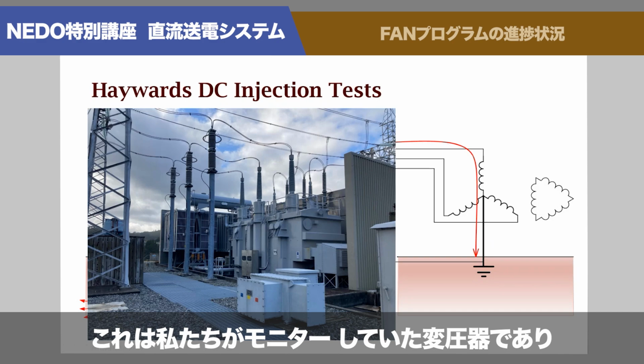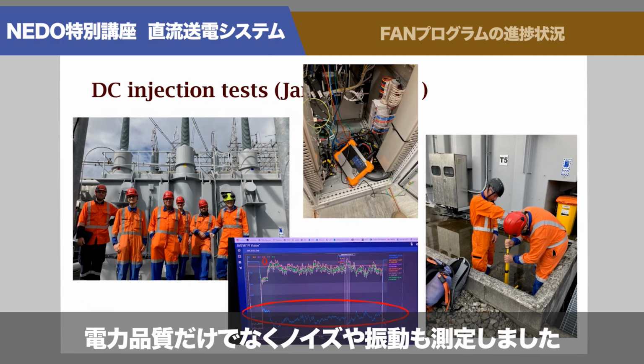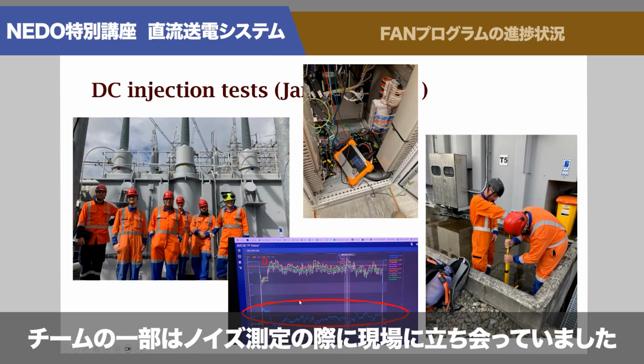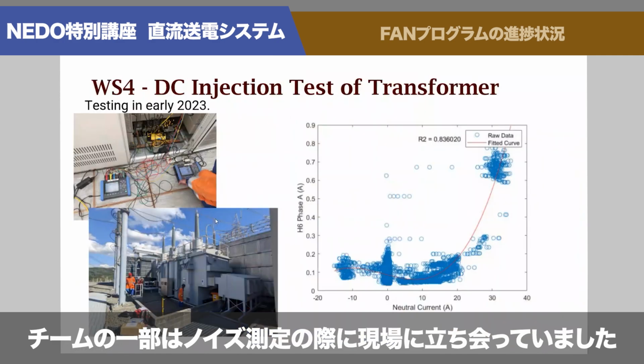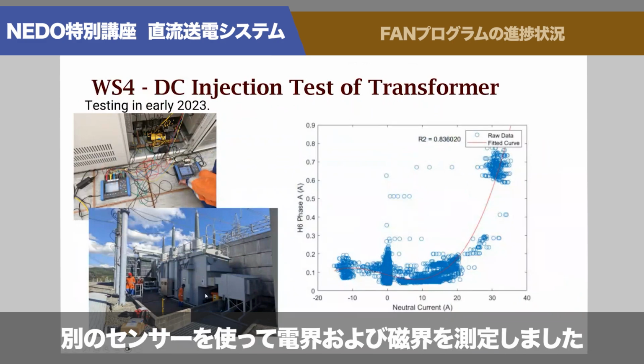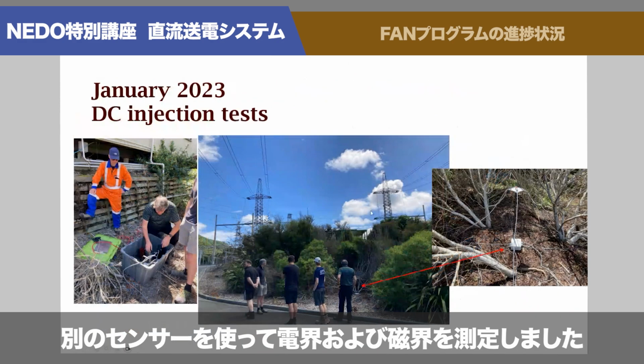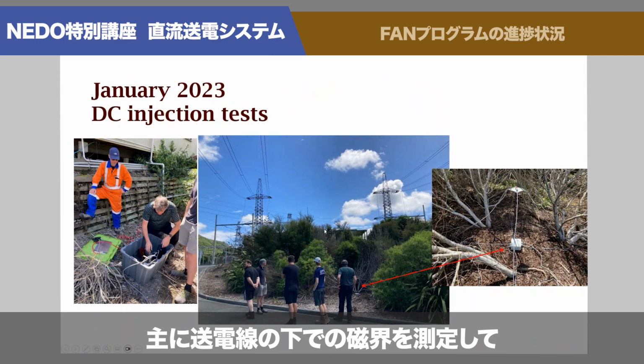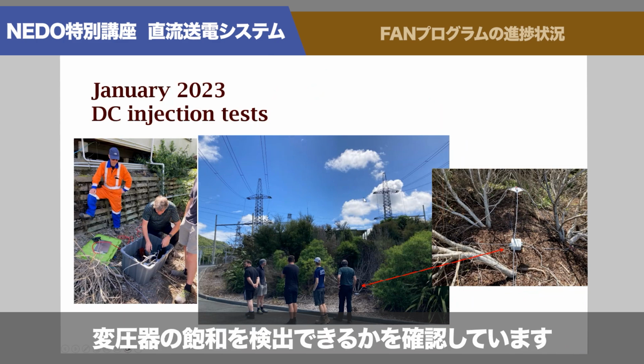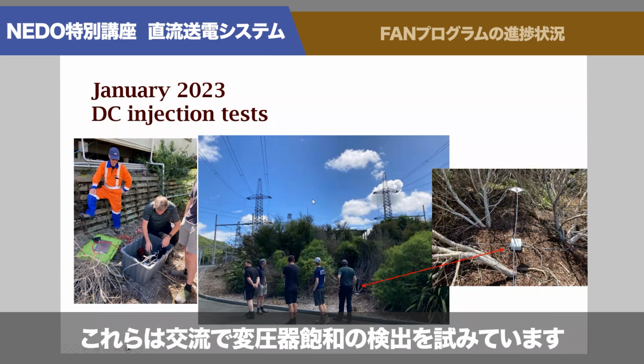This is the transformer we were monitoring and looking at. We not only measured the power quality, but we measured noise and vibration on it. Some of the plots, that's the team, part of the team also. That one there shows the noise measurements, and there's another sensor that got put there. We also measured, this is a pickup coil to measure the electric and magnetic fields, mainly magnetic fields under this transmission line going out. These are the AC lines, just seeing if we can detect the transformer saturation.